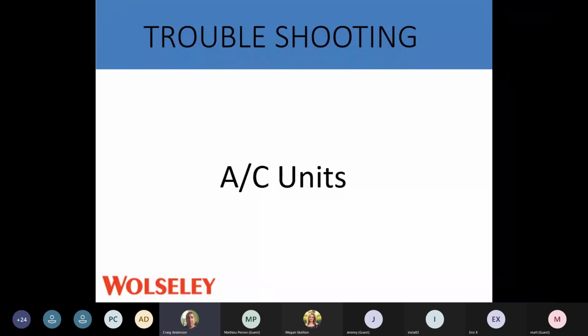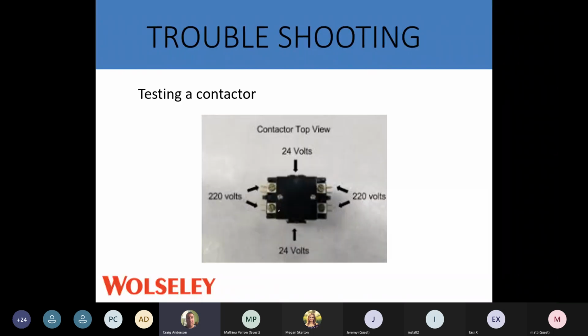So, a little troubleshooting of AC units. I always start with the contactor. I get calls every year on it. I have 220 to the outdoor unit and 24 volts. The contactor's pulled in and the air conditioner is not running.